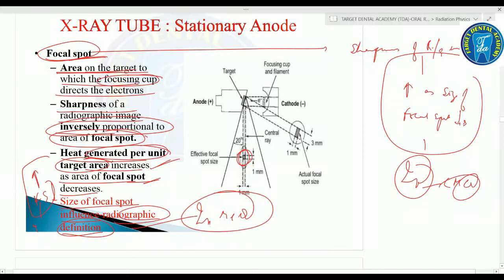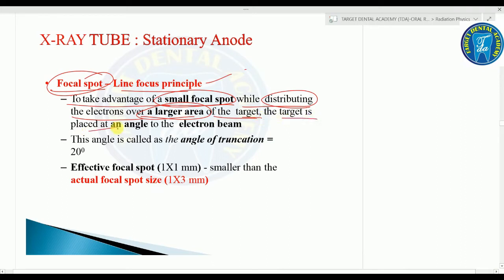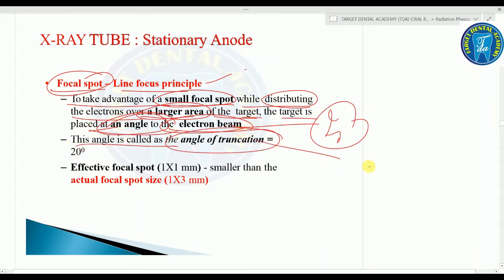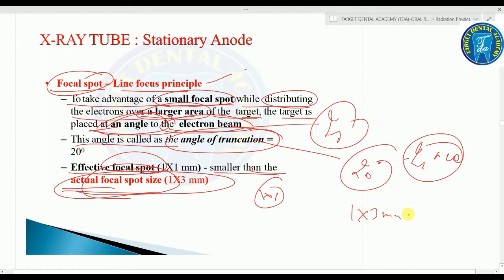If a question asks what the size of the focal spot influences, the answer is radiographic definition. Regarding the line focus principle: the target is placed at an angle to the electron beam — this angle is called the angle of truncation and is 20 degrees. The effective focal spot size is 1×1mm, while the actual focal spot is 1×3mm.